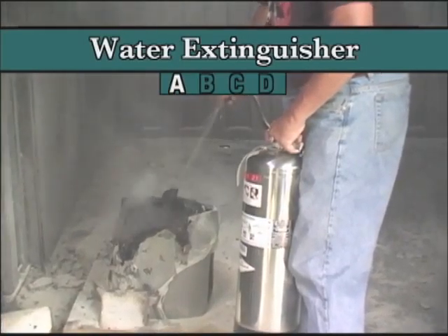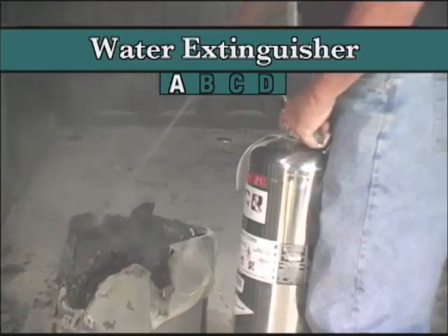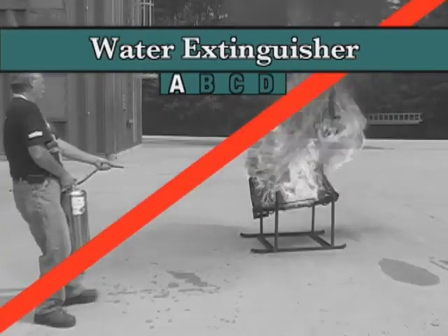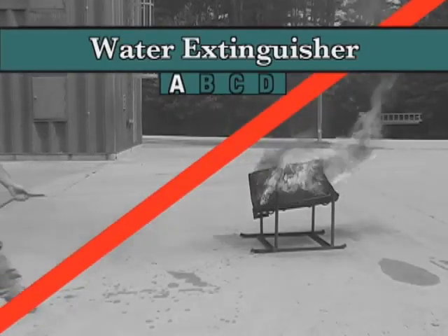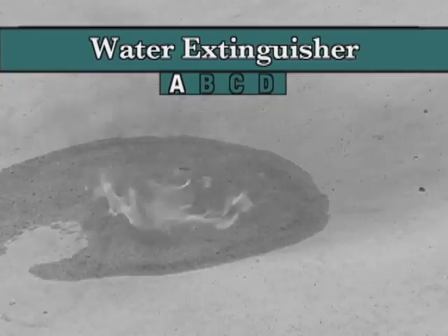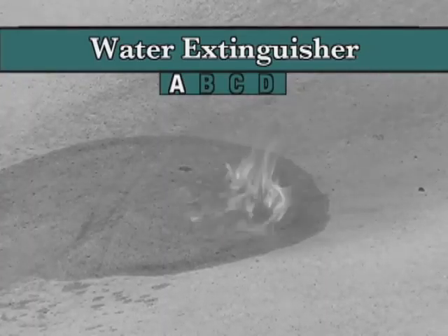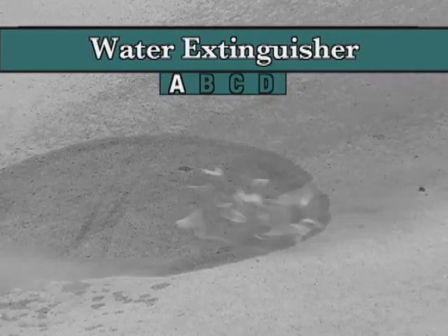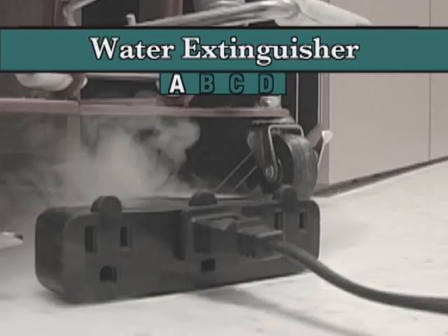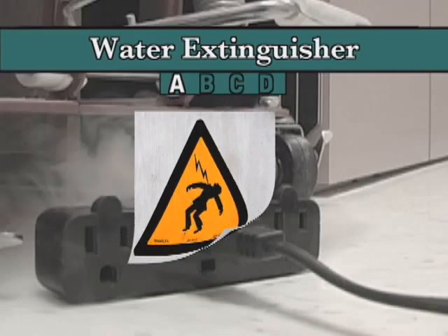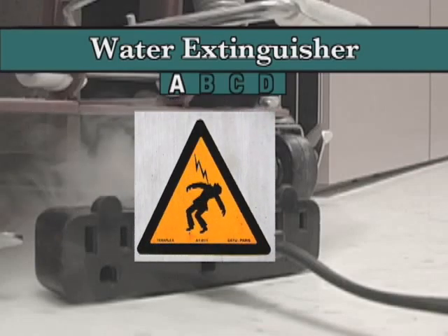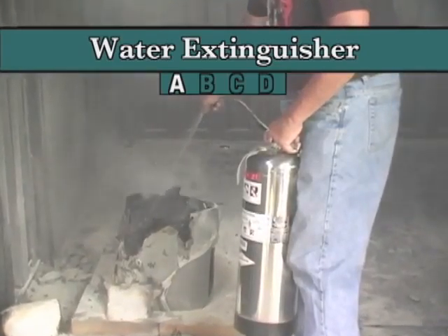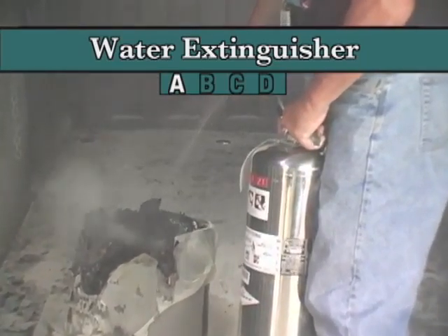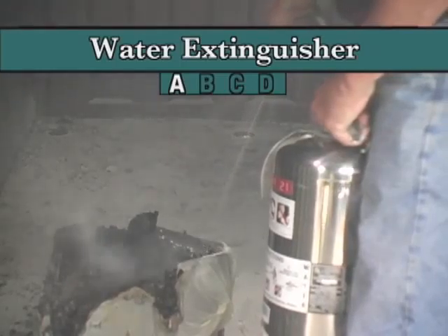Water extinguishers are suitable for Class A fires only. It's dangerous to use a water extinguisher on burning liquids such as gasoline or grease because the water will only spread the fire around, and it won't put it out. Water won't put out an electrical fire either, and the stream of water will conduct electricity right to you. You could be electrocuted.